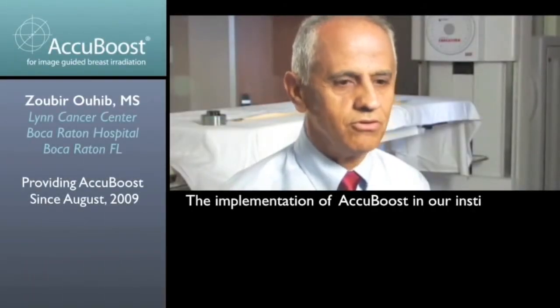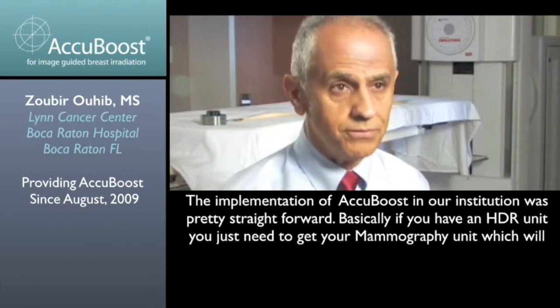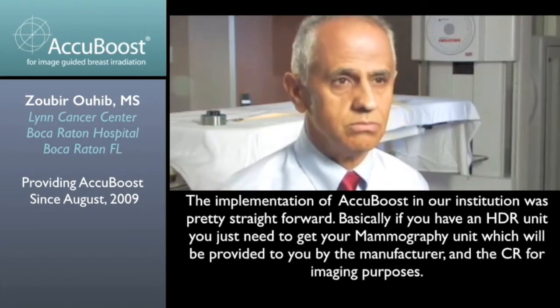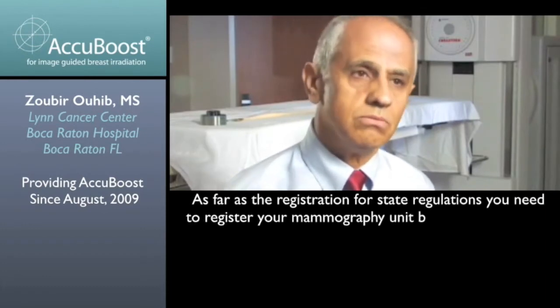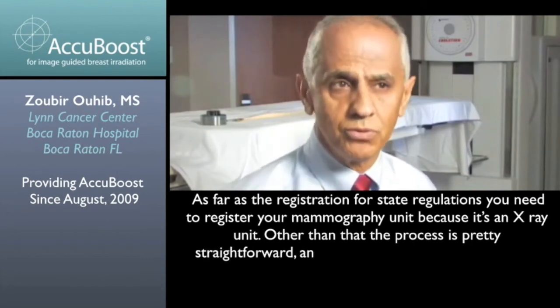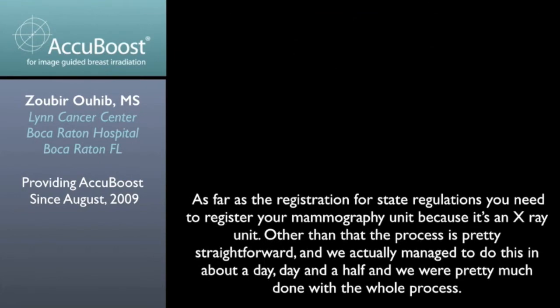The implementation of the AccuBoost in our institution was pretty straightforward. Basically, if you have an HDR unit, you just need to get your mammography unit, which will be provided to you by the manufacturer, and the CR for imaging purposes. As far as the registration for state regulation, you need to register your mammography unit because it's an X-ray unit. Other than that, the whole process is pretty straightforward, and we actually managed to do this in about a day, day and a half.